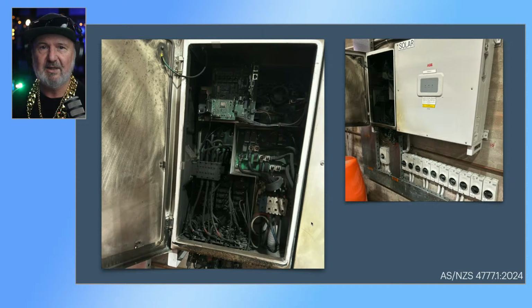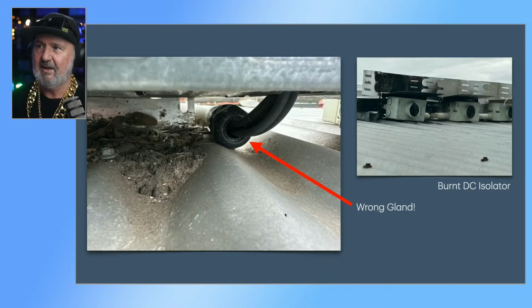How come it went from being just a problem on the roof to a problem that set the whole inverter's connection panel on fire as well? So pretty bad. So there you go. Use proper compression glands that seal. Don't enter from the top, because that's the other fault here. If you look again, that's looking down the roof, so water will run down. You can see all the sediment that's collected. It'll run straight in there with a heavy rain. So you're actually asking water to go in there. It's just terrible. So make sure that any entries to DC isolation or enclosures is on the downward side, properly sealed, and cross your fingers.